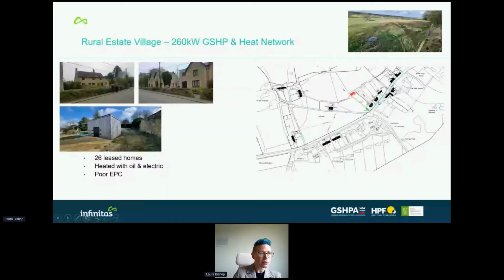They did some fabric upgrades, but the main project here was to install a 260 kilowatt closed loop horizontal array ground source heat pump system, delivering heat into a heat network to provide heating and hot water to these 26 homes. In the middle of this drawing we've got a red box - that's the energy centre, shown here in the photograph on the left. It's got 6 60-kilowatt NIBE heat pumps and some thermal stores. That's delivering into 3 separate heat network branches serving the variety of homes, and each home has a heat interface unit, an HIU, delivering heating and hot water.